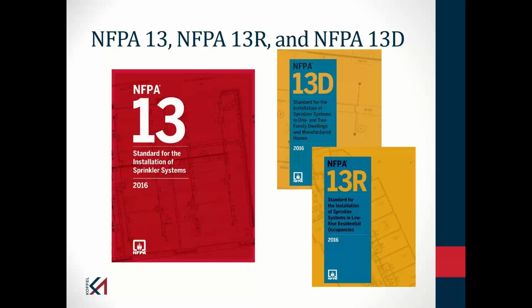So we don't want this in a high-rise building where a fire in that attic space would present a significant challenge to the fire department. But other than that, 13R more closely approximates NFPA 13. Again, I will typically calculate 4 sprinklers. It's a 30-minute water supply. But again, I do not have to have sprinklers in those concealed combustible spaces. So you may see some dorms on campus, in low-rise dorms, where you might be using a 13R system.